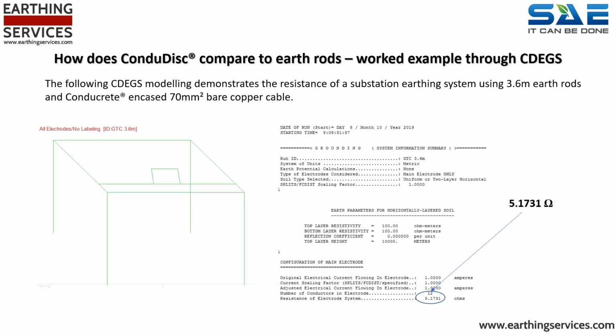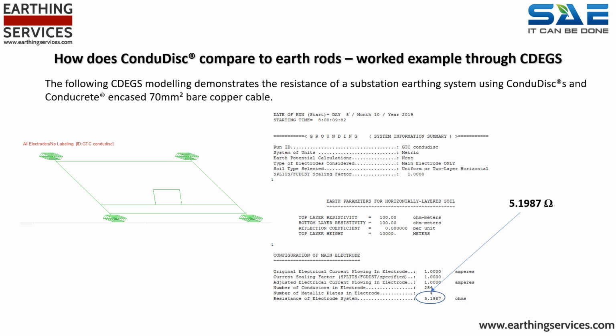So, how does the ConduDisc compare to earth rods? When it comes to designing earthing systems, the industry standard software that we use is called CDEGS. Here we can see the first stage of a CDEGS comparison between traditional earth rods and the ConduDisc. In this slide, we see the performance of a substation earthing system supported by 4-number 3.6 meter rods. And in this slide, we see those rods replaced with conjudiscs, which will be installed inside the cable trench, therefore removing the need for additional excavations or vertical driving.